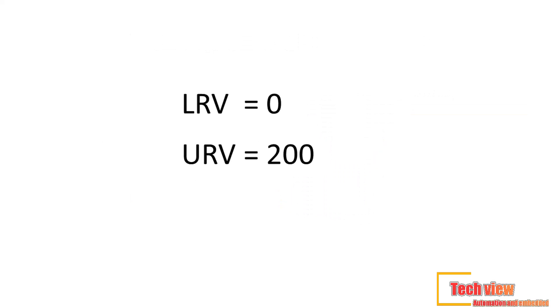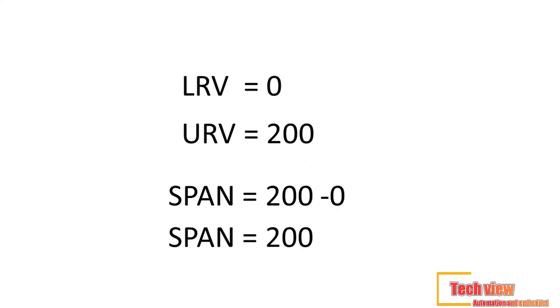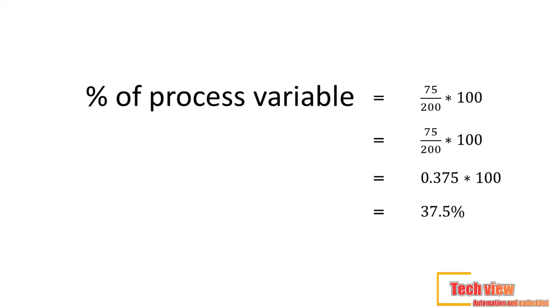For the above problem we have to find the percentage of the process variable. Our LRV equals 0 bar and URV equals 200 bar. The span is URV minus LRV, which equals 200 minus 0, equals 200. The current value is 75. The percentage of process variable equals current value divided by span, times 100. So 75 divided by 200 times 100 equals 0.375 times 100, which gives us 37.5%.